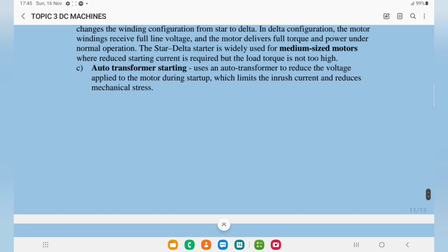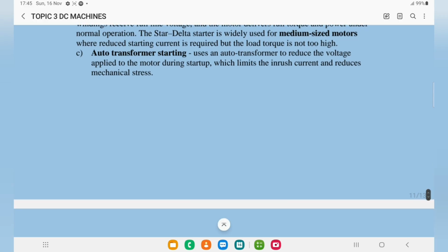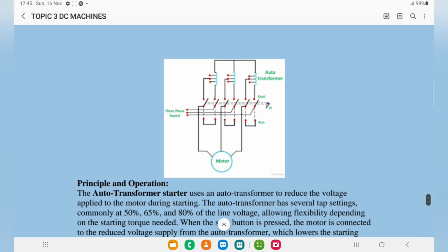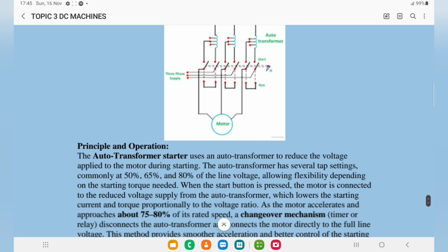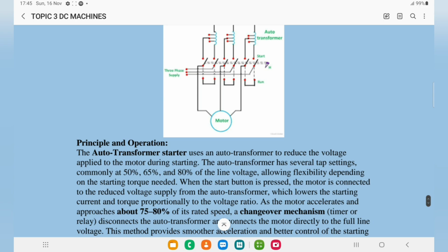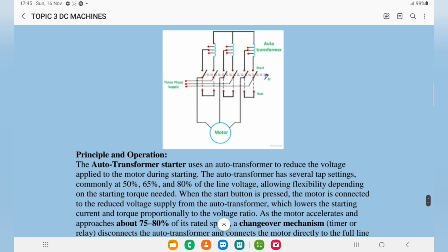We also have another method, which is autotransformer starting, whereby an autotransformer is used to reduce the voltage applied to the motor during startup, which limits the inrush current and reduces mechanical stress. There's a circuit diagram here for an autotransformer. It also has a three-phase supply system. We have the start and run components, and you also have the autotransformer.